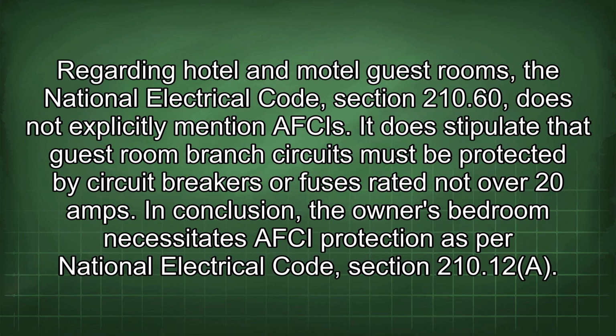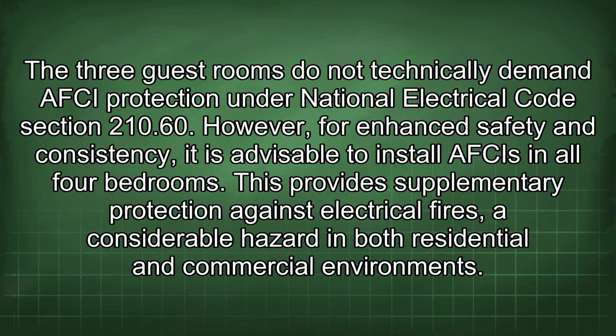Regarding hotel and motel guest rooms, the National Electrical Code, Section 210.60, does not explicitly mention AFCIs. It does stipulate that guest room branch circuits must be protected by circuit breakers or fuses rated not over 20 amps. In conclusion, the owner's bedroom necessitates AFCI protection as per National Electrical Code, Section 210.12(A). The 3 guest rooms do not technically demand AFCI protection under National Electrical Code Section 210.60.